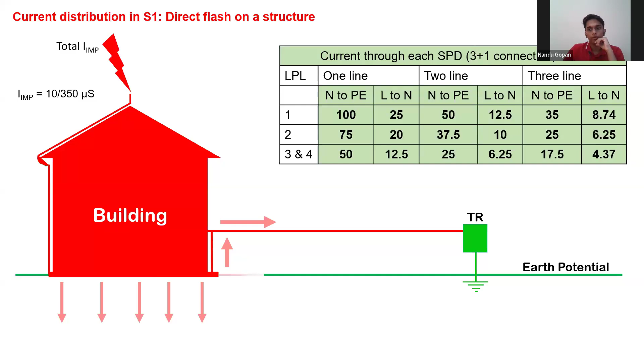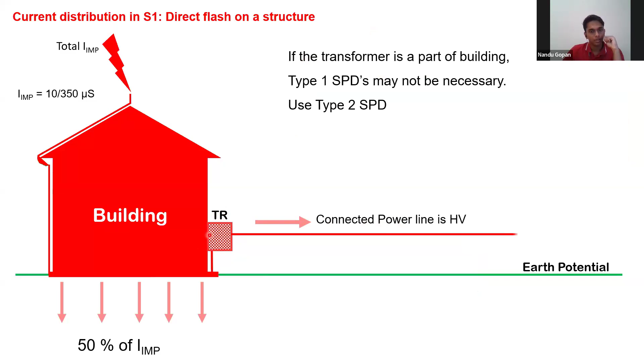Now, one more thing: suppose you have a structure, your lightning strike is connected here, and there is a transformer here with power connected to it. If the transformer is part of the building, inside the building, you don't need SPD1, you can also use SPD2 inside the building. Generally there will be some surge arresters on that side, so it's not a problem if it's inside the building. But if it's outside and the power lines are coming from the top, then you will need SPD1 here also.